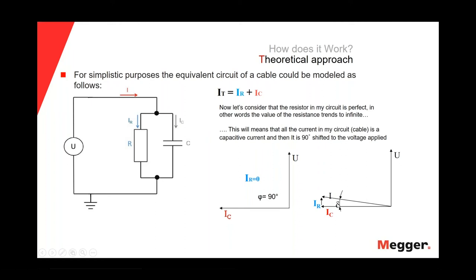And this angle, the delta angle, will be a good indication of how good or how bad the insulation in my cables is. This angle is a good indicator. If this angle tends to 90 degrees, that means that the insulation in my cable is aging. And if this angle tends to zero, that means that I have an almost perfect insulation. So the trigonometric function that correlates the resistive current and the capacitive one is the tan delta.